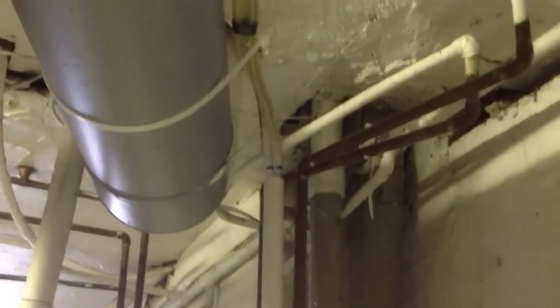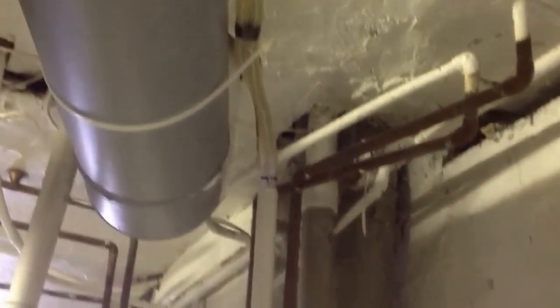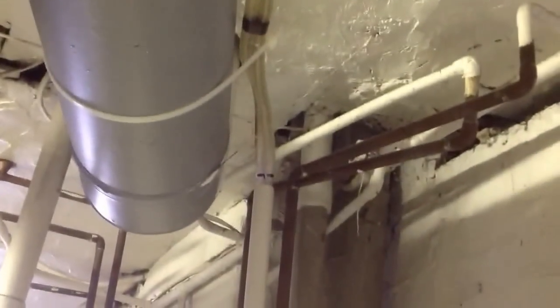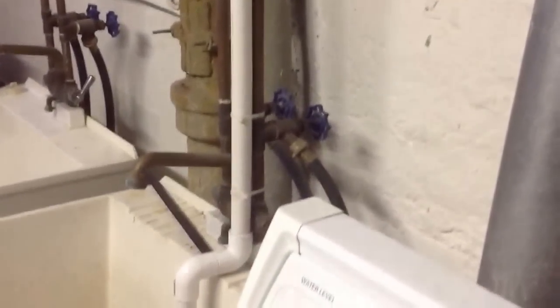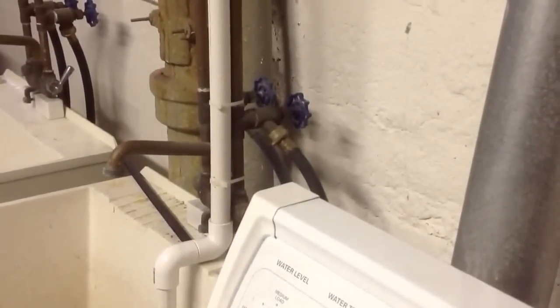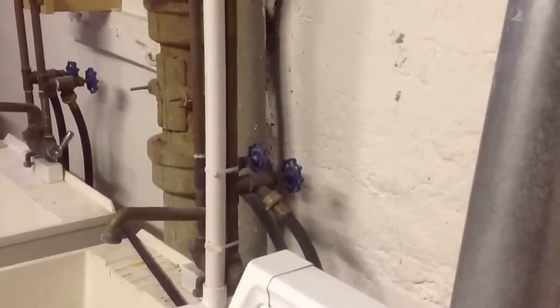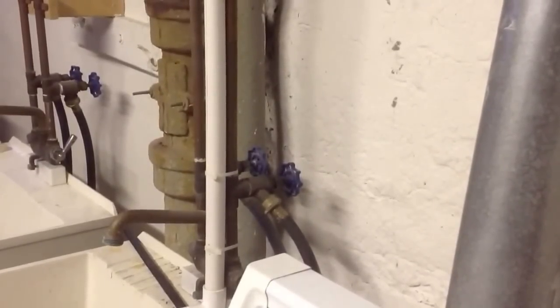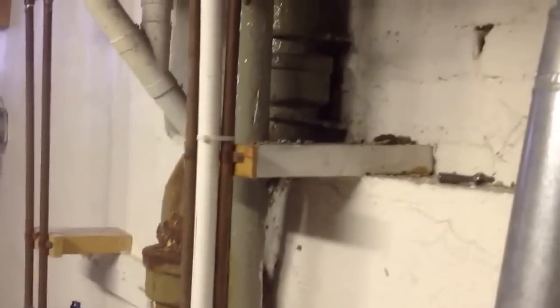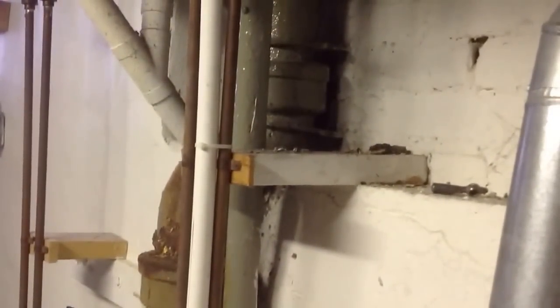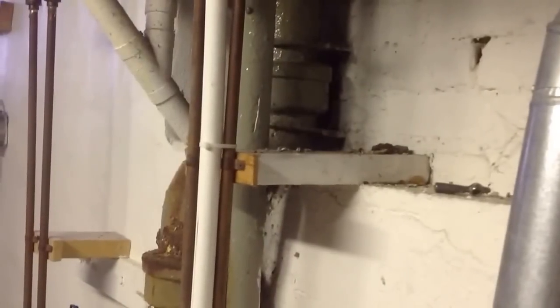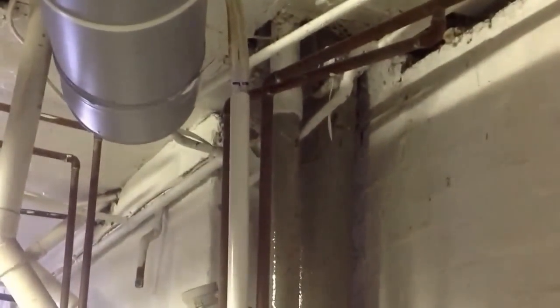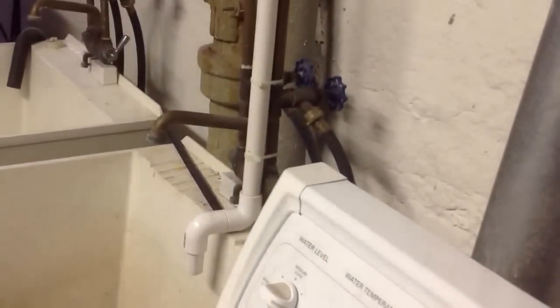This is a very good way to do that, nice and clean. I ran two pipes into that one inch and it drains out in the sink. It's a little better than just running your pipes and draining them in the sink. It's not good to run the plastic three-eighths flexible line directly into a drain because you don't have a trap and it's kind of not appropriate. But this is an acceptable way to do it. You can run your three-eighths line over and drain into the sink.